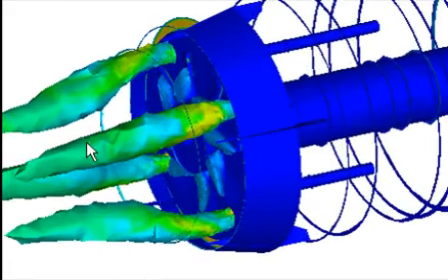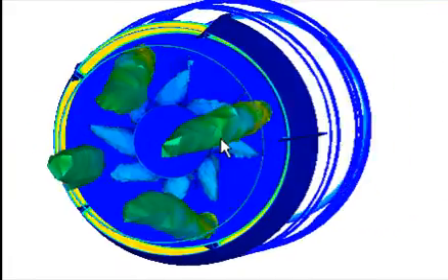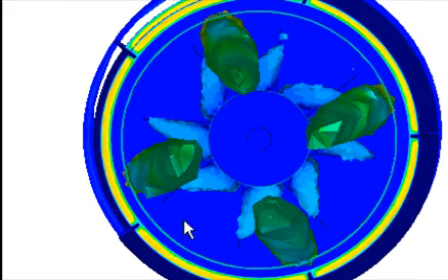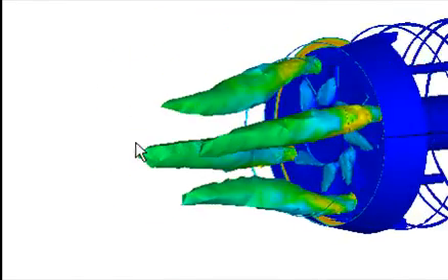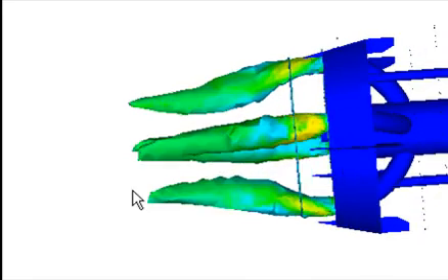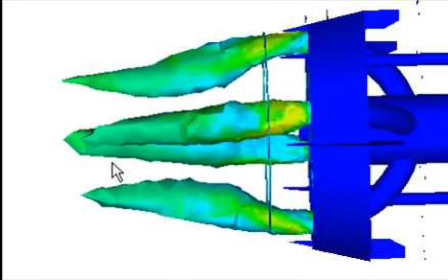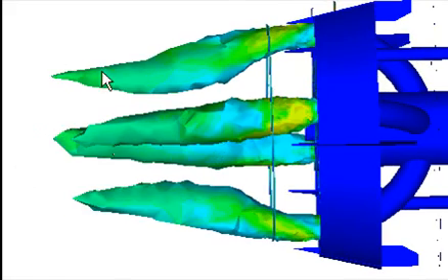One of the best things in CFD design is that we can compare the results of many simulations, for example geometry or boundary condition what-if scenarios in one single window. It can be analyzed what difference it will make if the volume flow rate of air and gas is increased. Looking at the same gas concentration level, the length of gas jets is different. Based on the design comparisons it can be decided which way to go during product development.